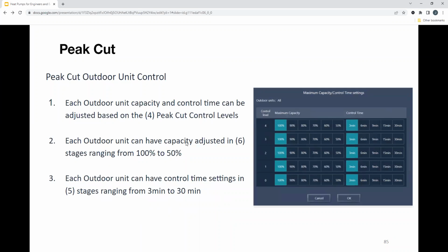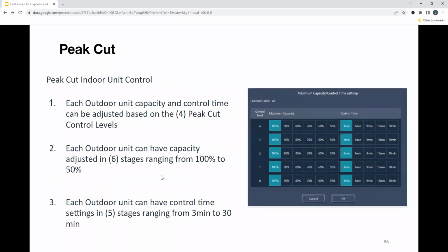And you can do the same thing with your outdoor units, right? You have different options. You can set the capacity, whether that be 100% all the way down to 50%, with percentages in between. And then you can set control times. For example, I only want peak cut to be controlled every 15 minutes, or for a duration of 15 minutes. So you're able to do that as well. If you are trying to reduce your kilowatts and utilities are trying to give you incentives on that, you can choose to do this to get some kind of incentive cash during peak hours. And then you can do the same thing with your indoor units based on percentages.